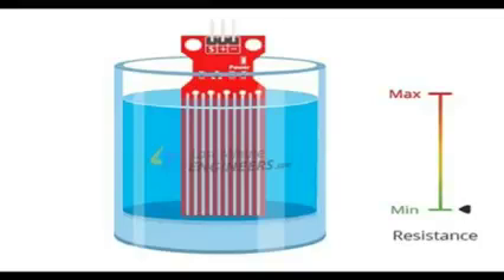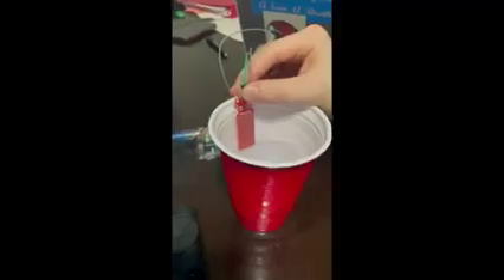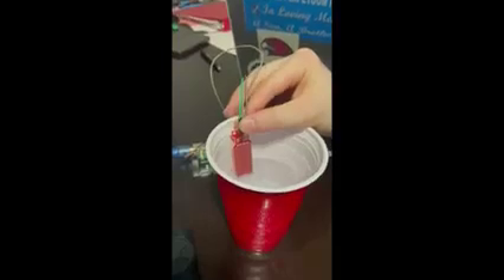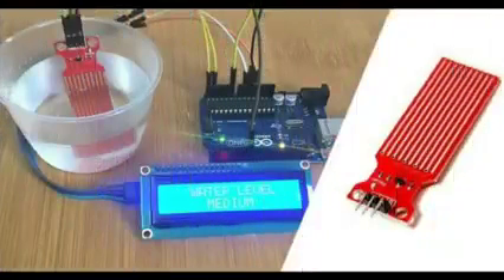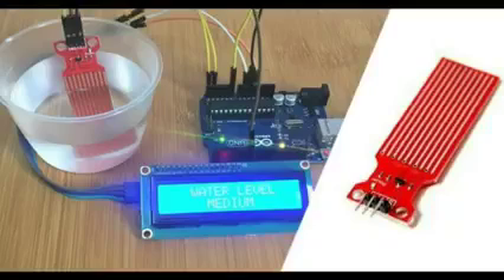The series of exposed parallel conductors together acts as a variable resistor, just like a potentiometer, whose resistance varies according to the water level. The change in resistance corresponds to the distance from the top of the sensor to the surface of the water. The resistance is inversely proportional to the height of the water. More water immersion results in better conductivity and lower resistance, while less water immersion results in poor conductivity and higher resistance. The sensor produces an output voltage according to the resistance, which by measuring we can determine the water level.